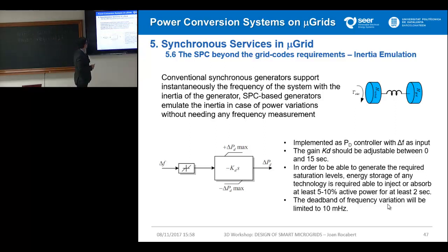This is the filtered frequency of the grid. It passes through a dead band, and from this we get the H of the inertia that we want to emulate. This H, for the requirement, should be between 0 and 15 seconds.